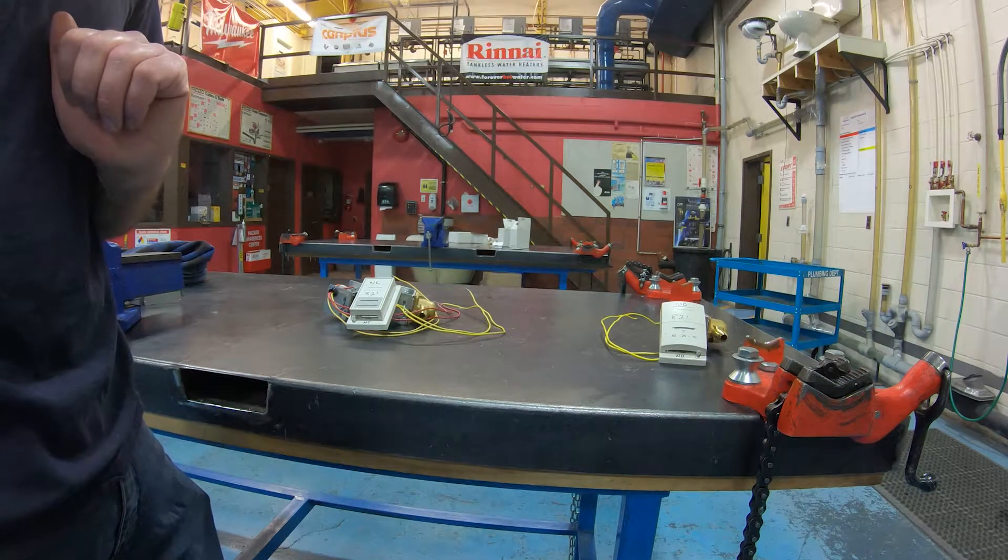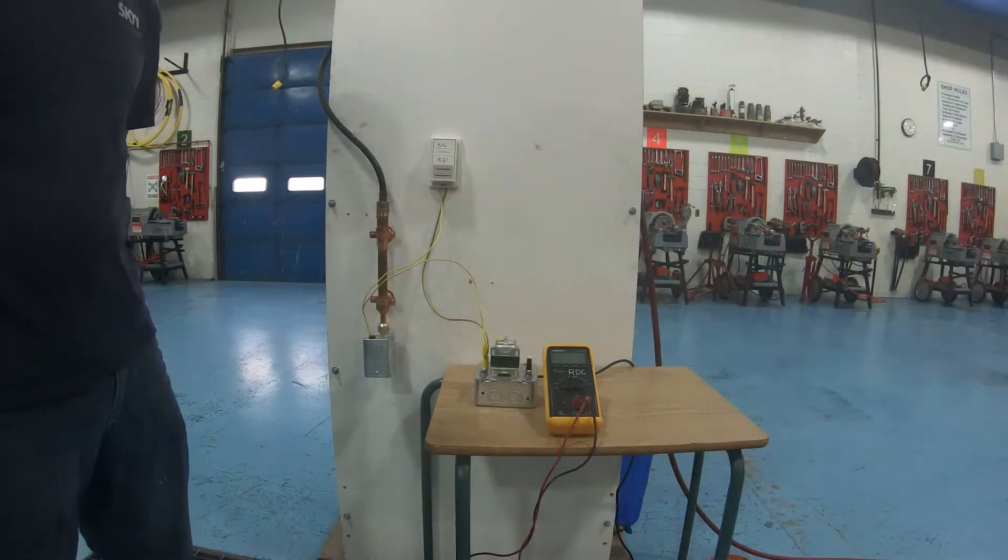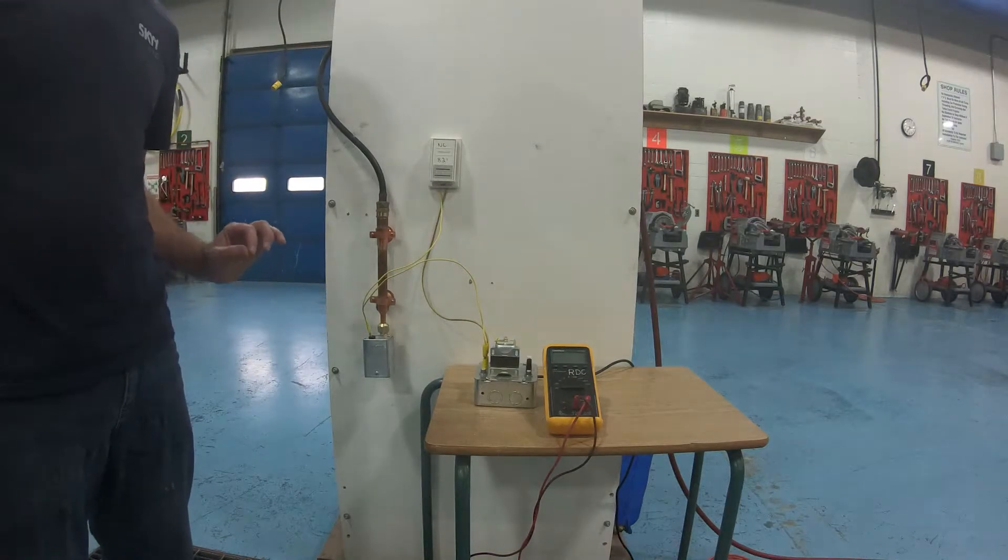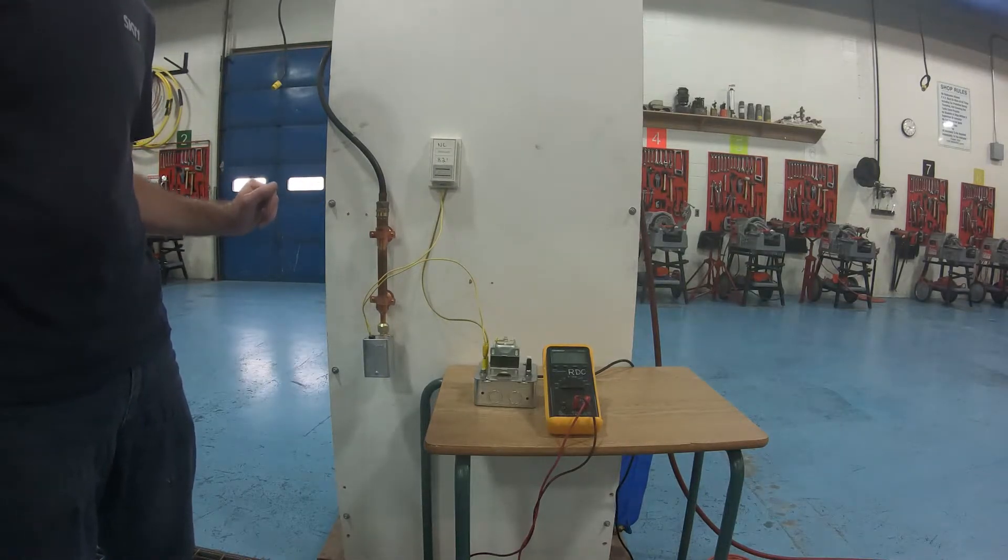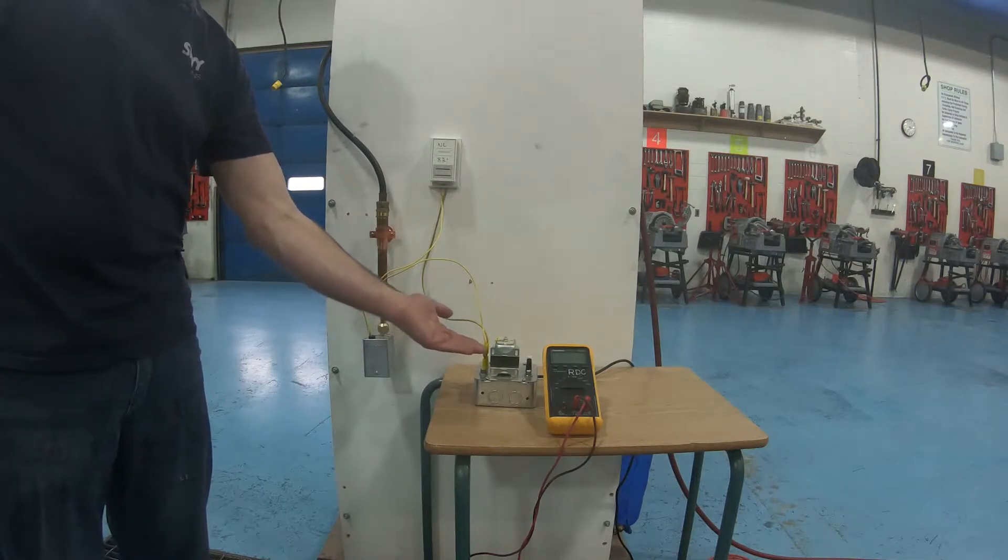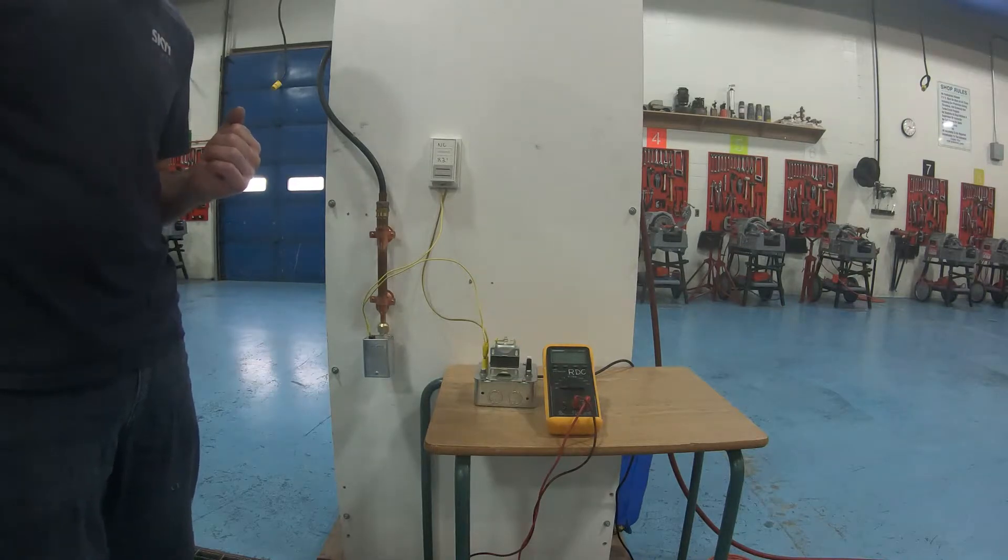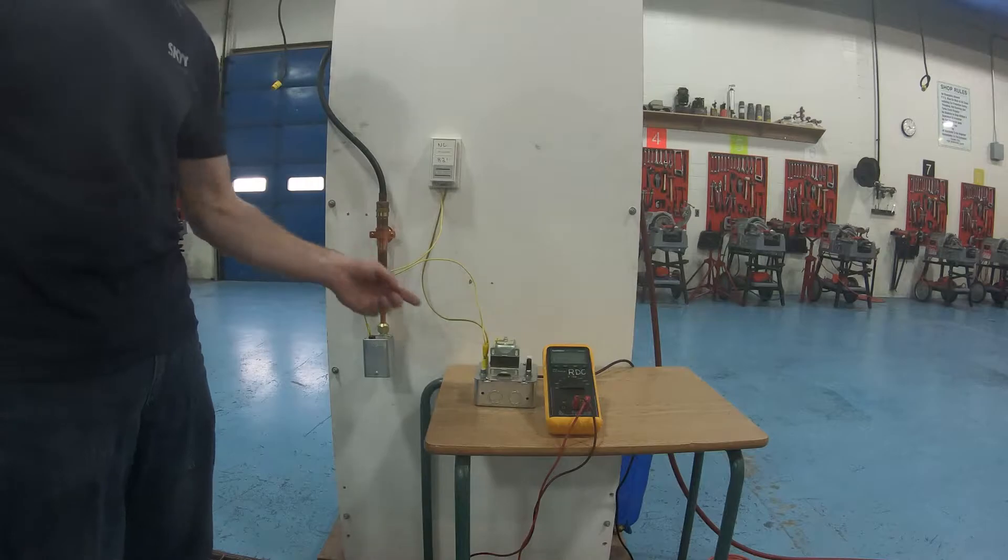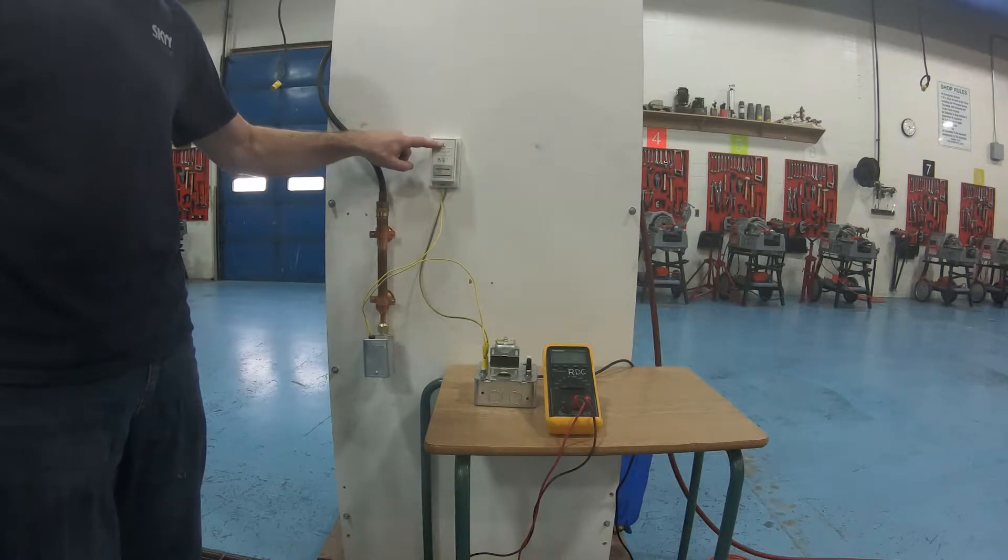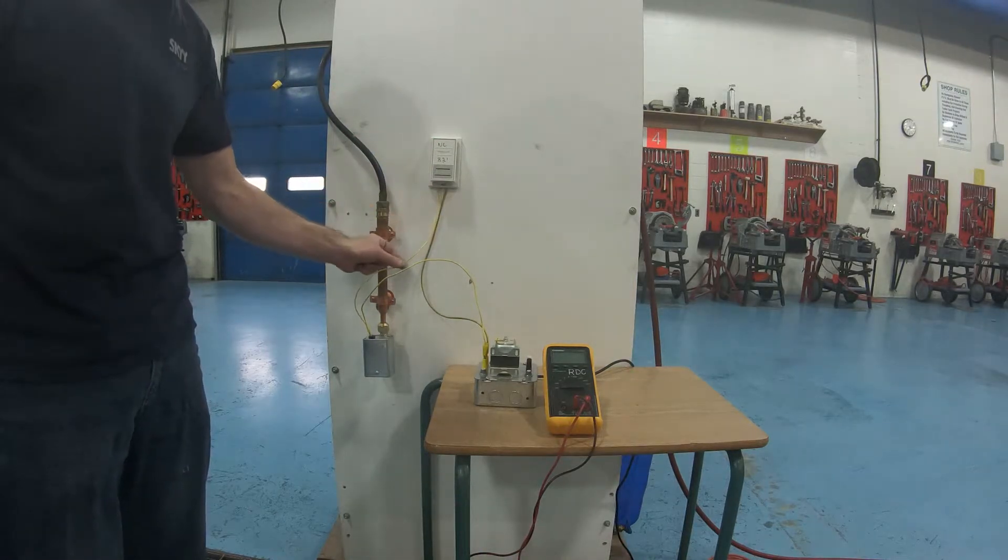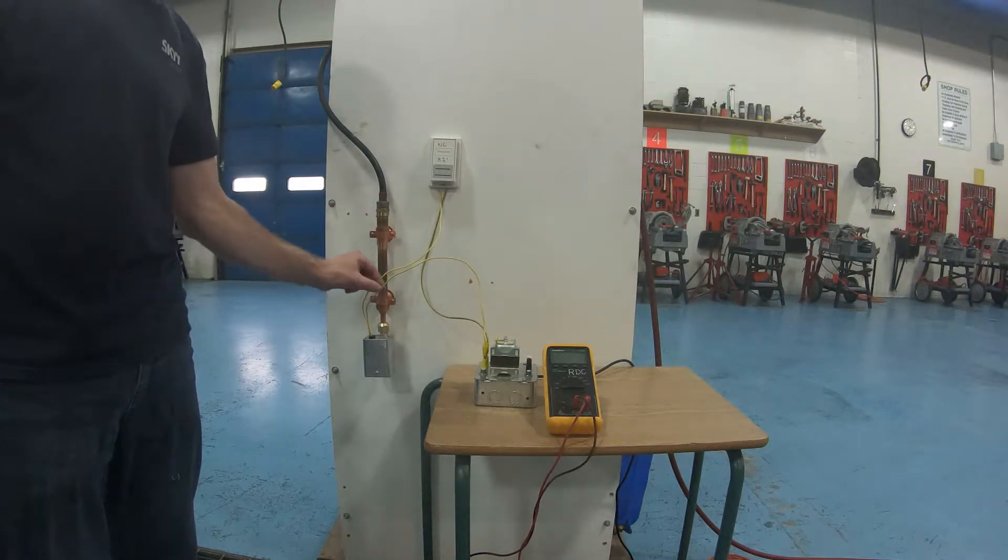Now let's see them in action. This is my normally closed zone valve. This is just a standard normally closed zone valve. I only have two power leads coming out of it, so there is no end switch. What I have here is a 24 volt transformer which is just converting power from your house, which is about 120, and turns it into 24 volts. So what I have here is power coming out of my transformer to the thermostat, which is just a typical switch that is temperature activating.